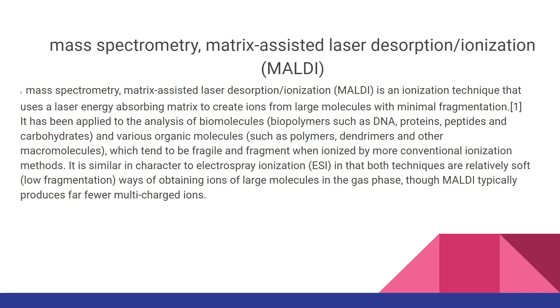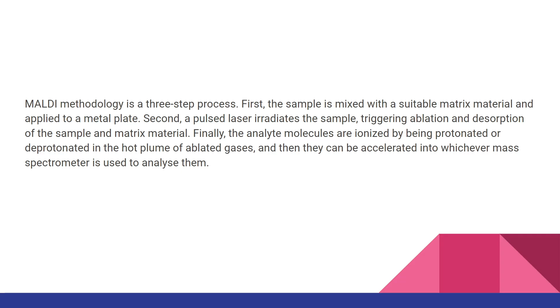MALDI methodology is a three-step process. First, the sample is mixed with a suitable matrix material and applied to a metal plate. Second, a pulsed laser irradiates the sample, triggering ablation and desorption of the sample and matrix material. Finally, the analyte molecules are ionized by being protonated or deprotonated in the hot plume of ablated gases, and then they can be accelerated into whichever mass spectrometer is used to analyze them.